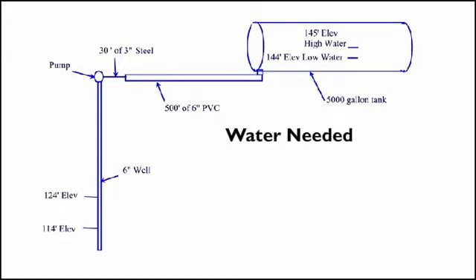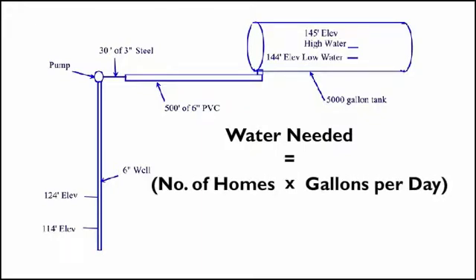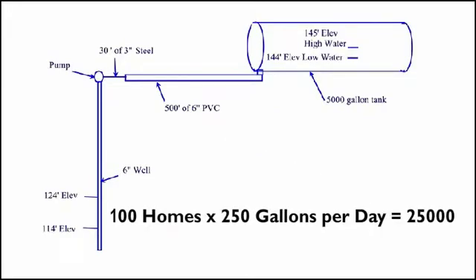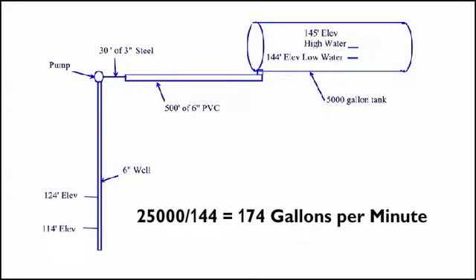The water needed is calculated as follows: the number of homes multiplied by gallons per day divided by 144. If we assume the water use of 250 gallons per day, our well needs to provide 174 gallons per minute.